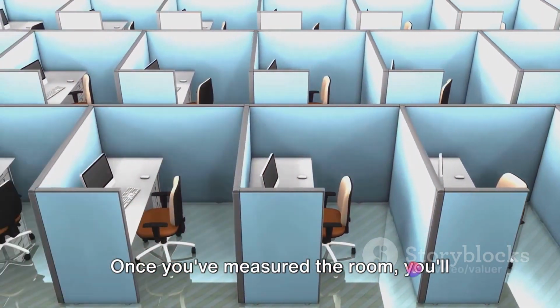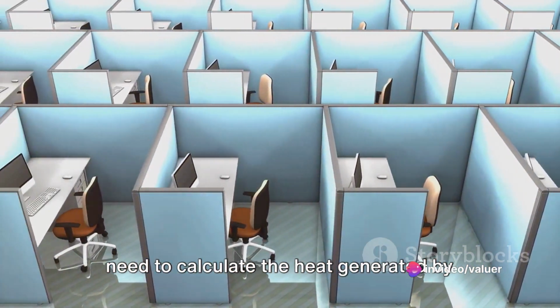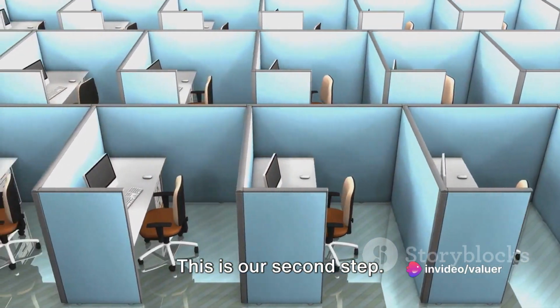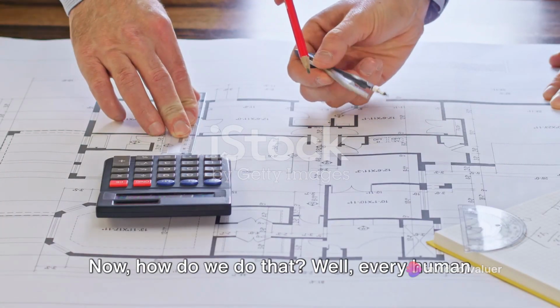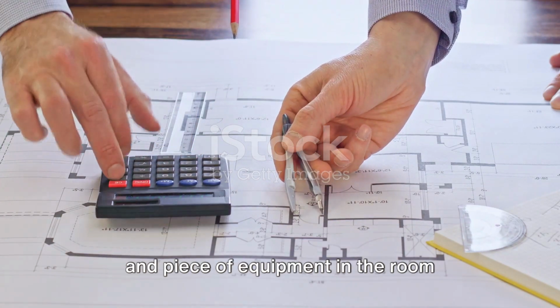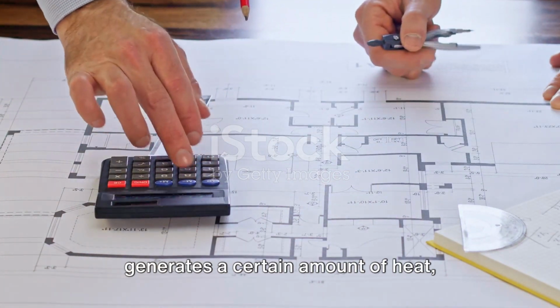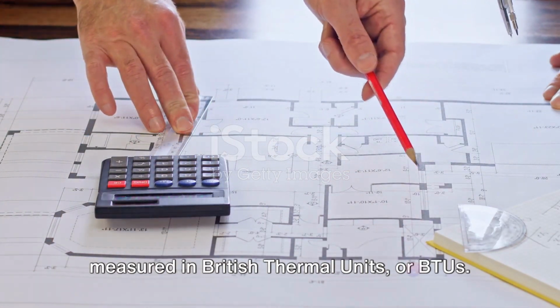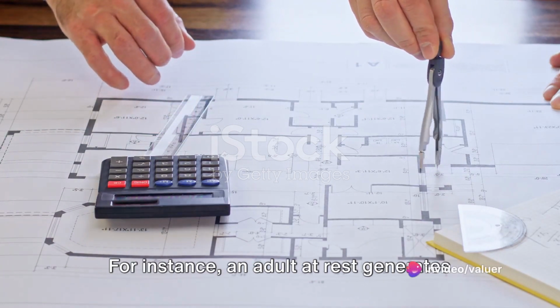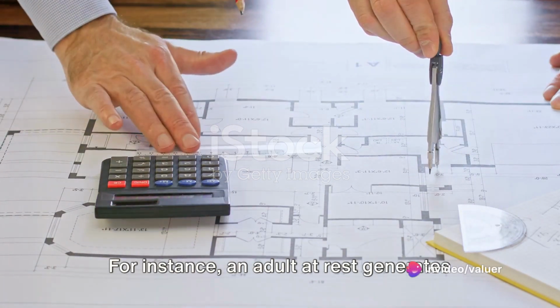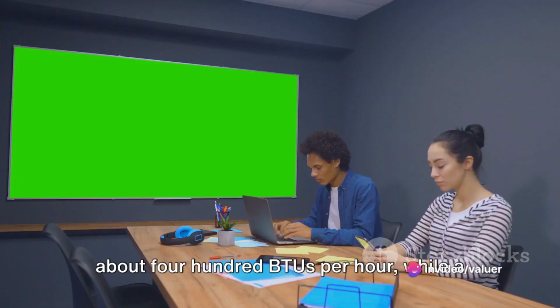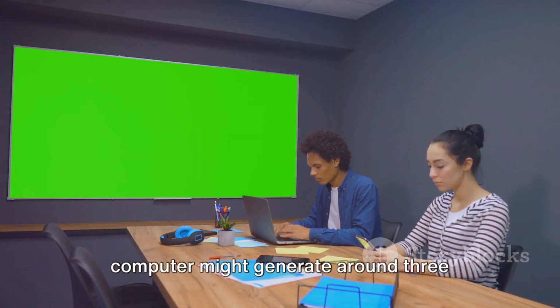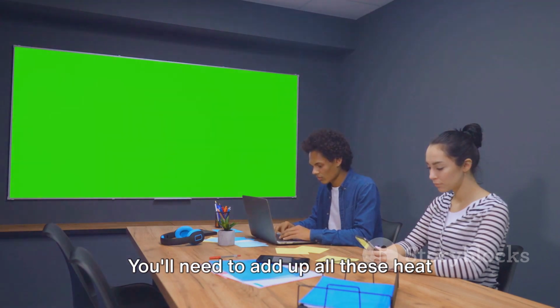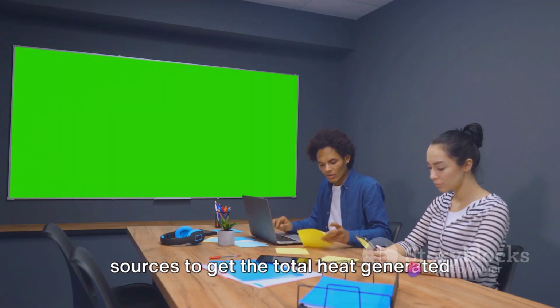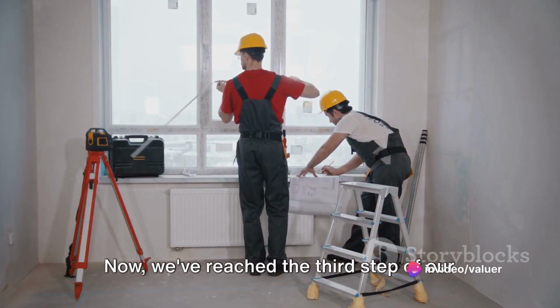Once you've measured the room, you'll need to calculate the heat generated by occupants and appliances. This is our second step. Now, how do we do that? Well, every human and piece of equipment in the room generates a certain amount of heat, measured in British thermal units, or BTUs. For instance, an adult at rest generates about 400 BTUs per hour, while a computer might generate around 300 BTUs per hour. You'll need to add up all these heat sources to get the total heat generated within the room.